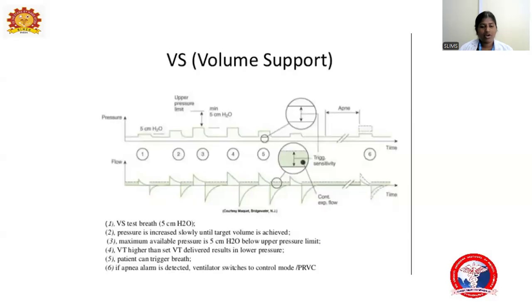And if the tidal volume by the patient is higher than the tidal volume that is set, it will result in a lower pressure. The patient can trigger the breath, as in the fifth step. If the patient is not breathing and the apnea alarm is detected, the ventilator automatically switches to the control mode.